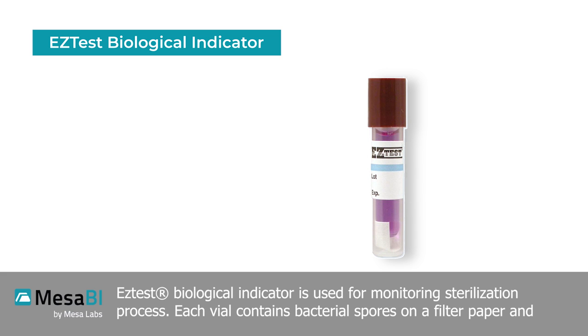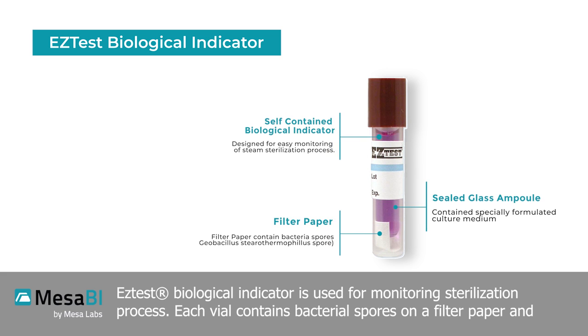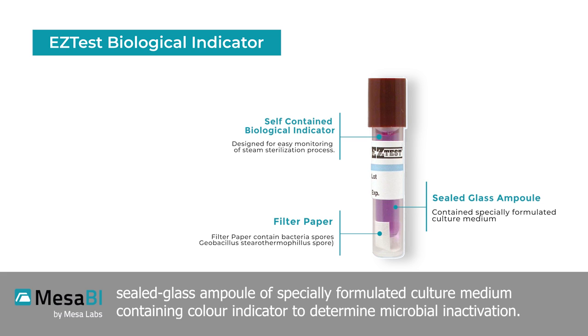The EZTest biological indicator is used for monitoring sterilization processes. Each vial contains bacterial spores on a filter paper and a sealed glass ampoule of specially formulated culture medium containing a color indicator to determine microbial inactivation.